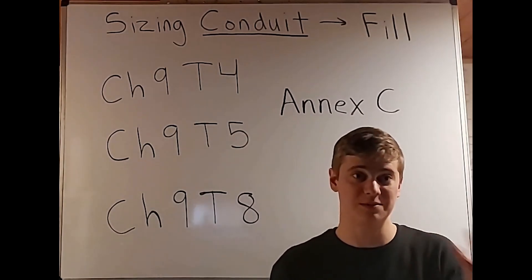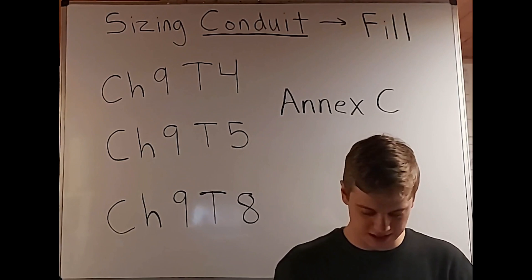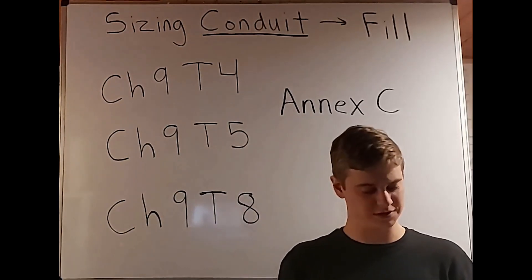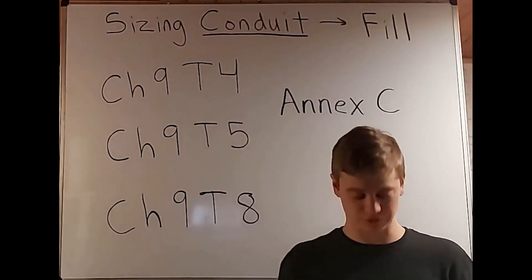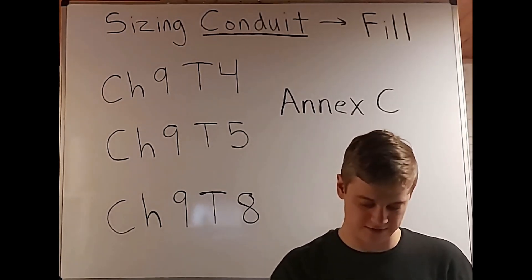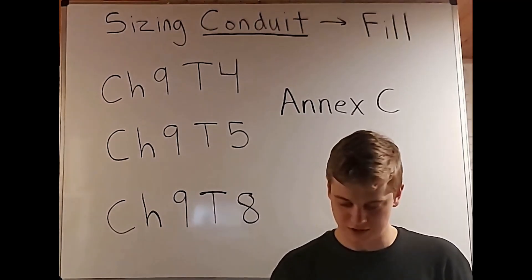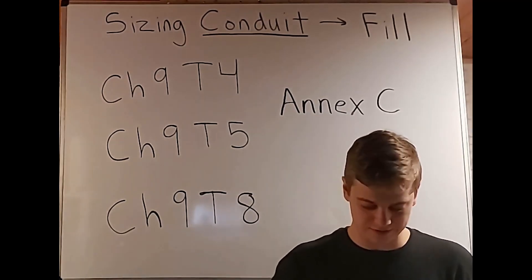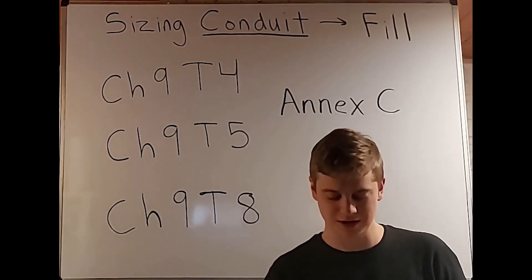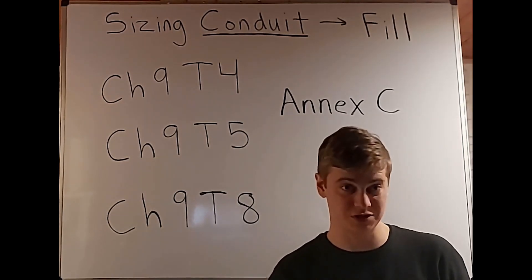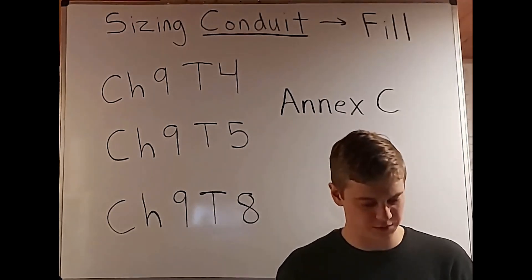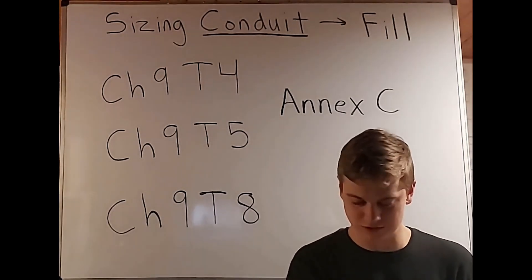So now we know how to size certain types of wire using Table 5. For example, if you have three THHN and four THWN-2 conductors, you go to Chapter 9, Table 5 and look up your size in AWG or KCmil — whether that's 14 gauge, 2/0, or 500 KCmil. On the right-hand side, you'll see millimeters squared, but more commonly you'll use square inches, listed under the 'approximate area' column.